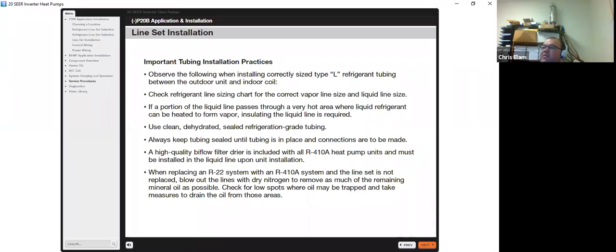Important tubing installation practices. Observe the following when installing correctly sized type L refrigerant tubing. Check the refrigerant line size chart to ensure that you have the correct vapor and liquid size. If a portion of the liquid line passes through a hot area where liquid refrigerant can be heated to form vapor, insulating the liquid line is required.